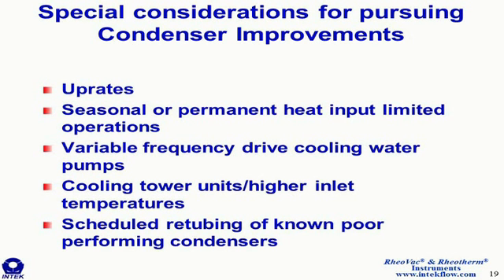If the unit has a scheduled retubing and is known to be a poor performing condenser, then when the unit is being retubed, that is the optimal time for implementing a condenser retrofit, because all of the tubes are out. You have more flexibility to alter the interiors of the condenser, and you also have a crew already on site doing the retubing. They have the skills necessary to install a condenser retrofit, so there's labor savings there. Also, if it's a retrofit of similar design to one we've done before, then there may be some engineering evaluation reduction.